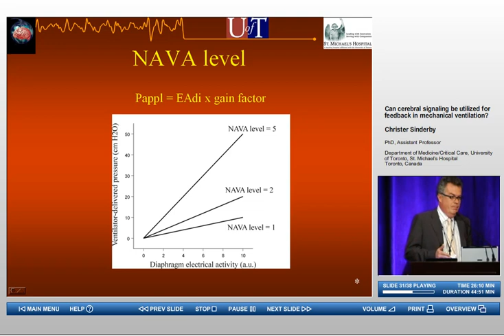So, to set the gain, it's pretty easy. You look here on the y-axis, you can see the ventilator-delivered pressure, and you see the diaphragm activity. So if we say that the diaphragm activity goes from 0 to 10, and we have a level of 1, it means the pressure will go from 0 to 10 in the breath. If we double the level, so we go to level 2, well, the same activity, 0 to 10, will go from 0 to 20. So you're just going to turn this factor up, and you get, for a given activity at any point in the inspiration, more pressure. So it's not very difficult.